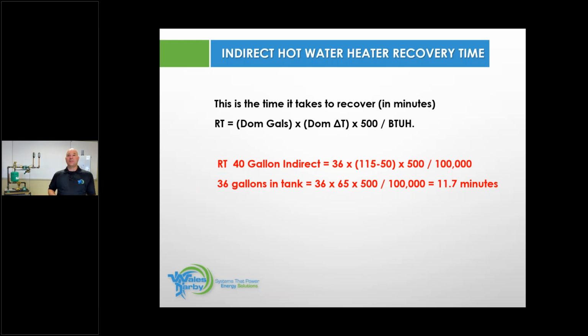So I'll bring in some numbers here. Delivery temperature: I want to deliver the water leaving that indirect at 115 degrees to the home. The incoming water to the home is 50 degrees. So that's in parentheses, right? We're going to do that math first. There's our 500, there's our boiler size.